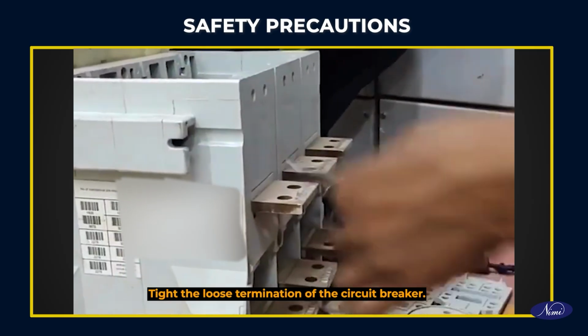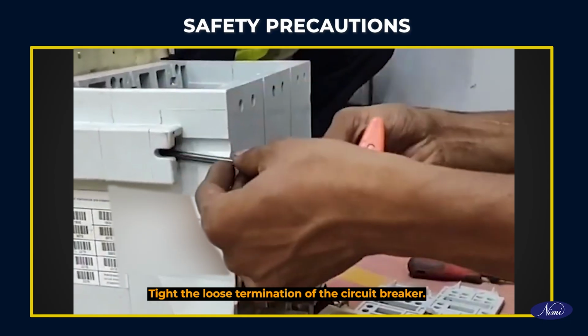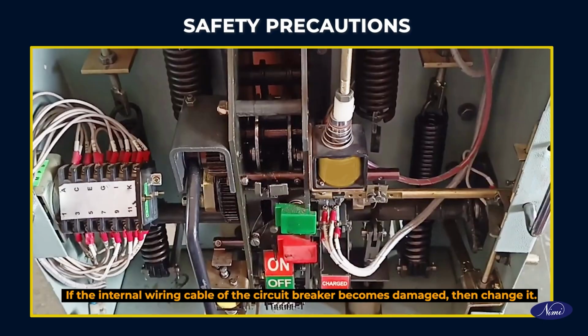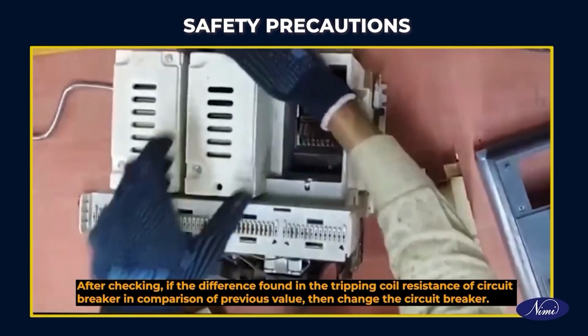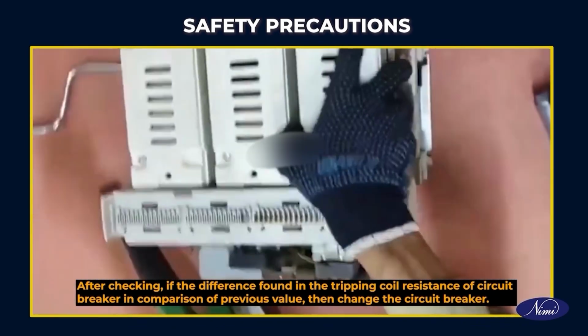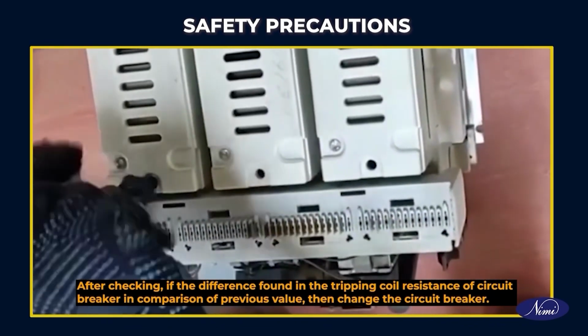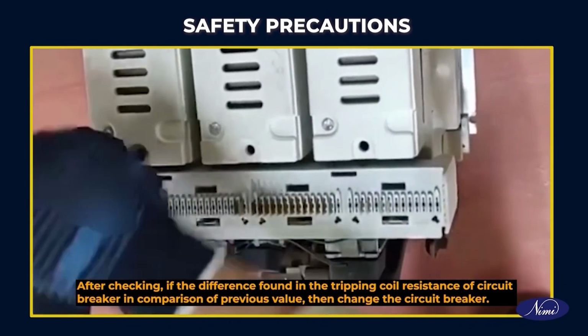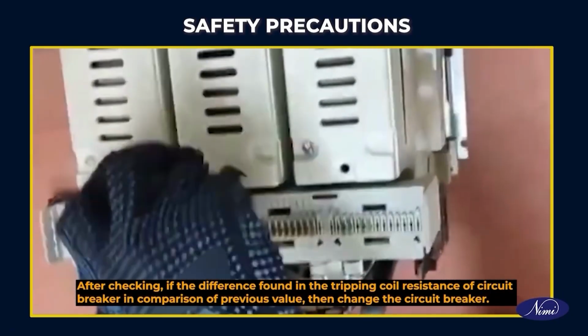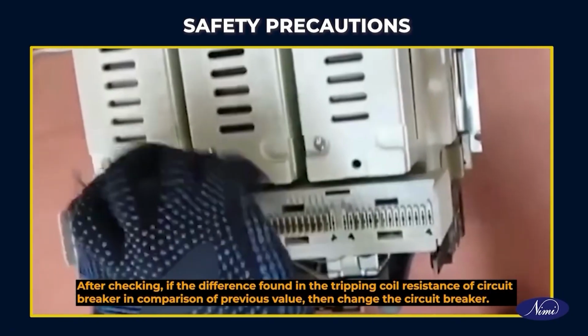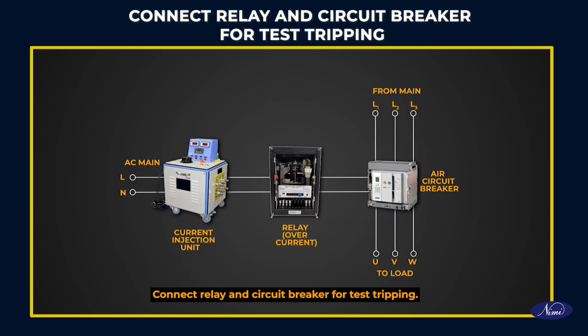Tighten the loose termination of circuit breaker. If the internal wiring cable of the circuit breaker becomes damaged, then change it. After checking, if a difference is found in the tripping coil resistance of circuit breaker in comparison to the previous value, then change the circuit breaker.